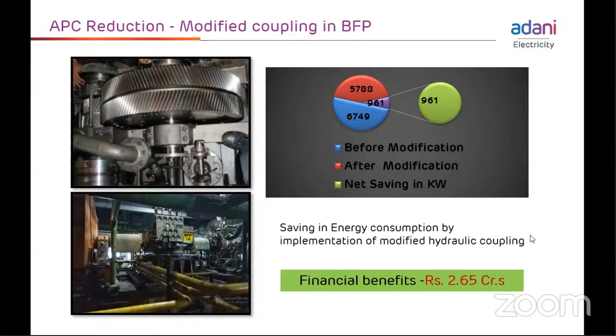All these thermal power stations need to back down in the night hours or during low load period. So whenever there is a back down or low load, the boiler feed pump has high slip losses in the hydraulic coupling. Most of you may be aware of the type of slip losses happening in hydraulic couplings.